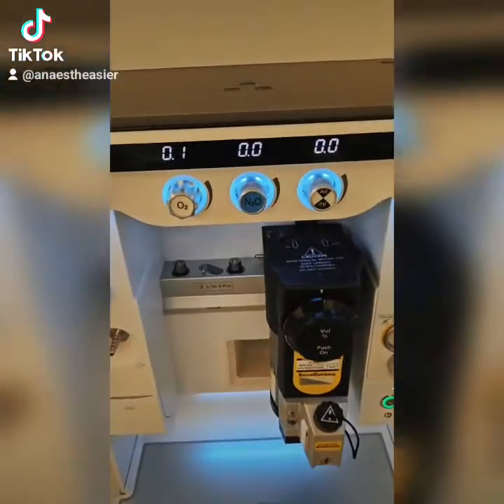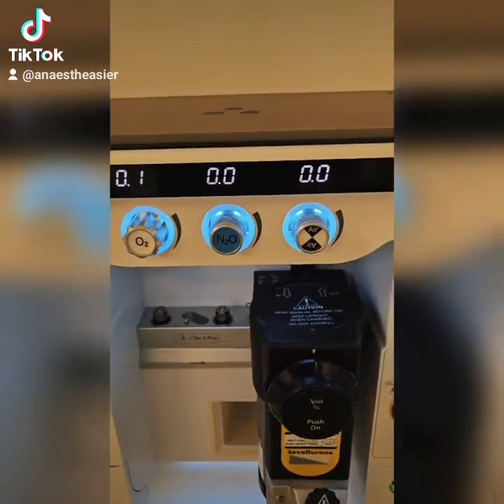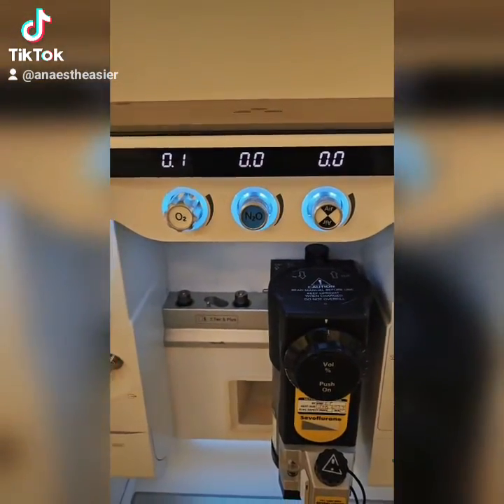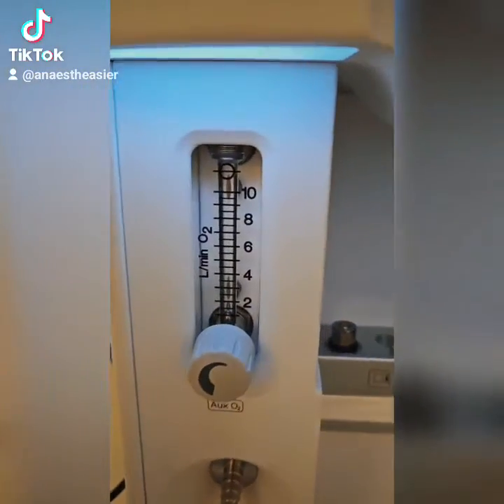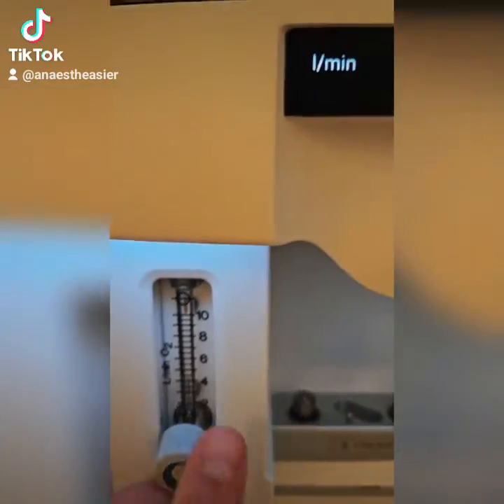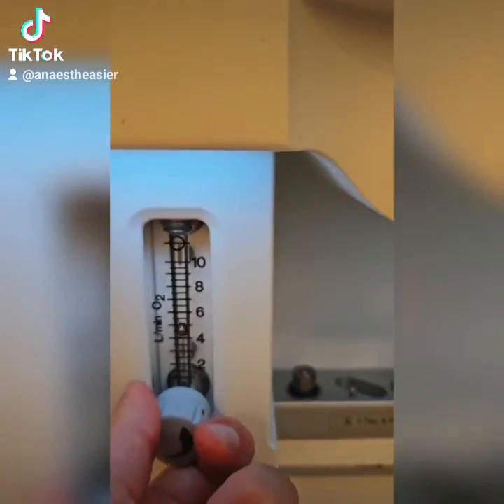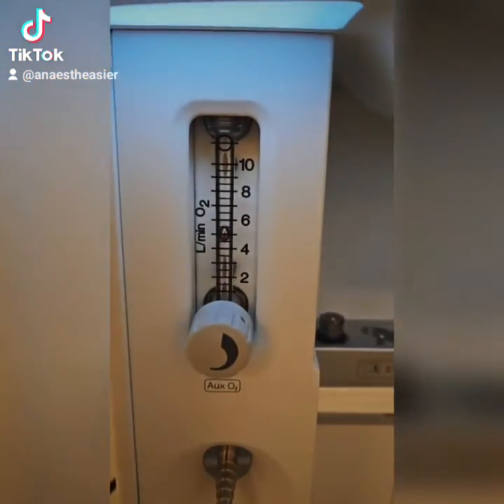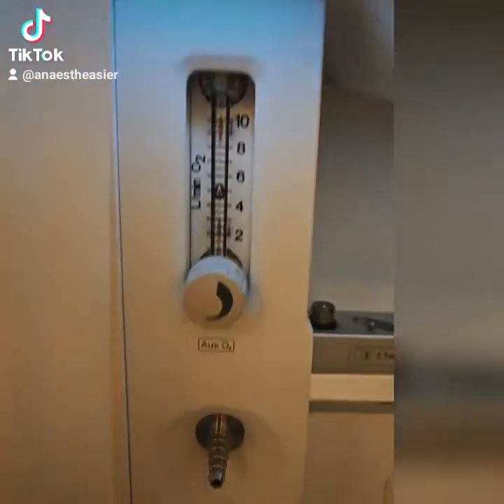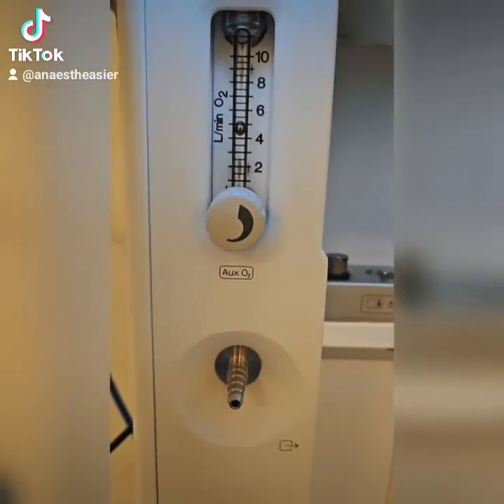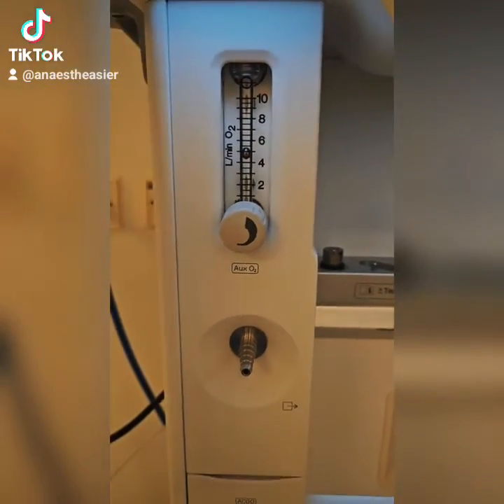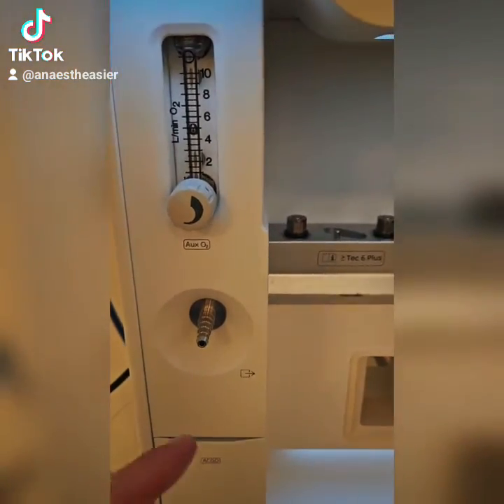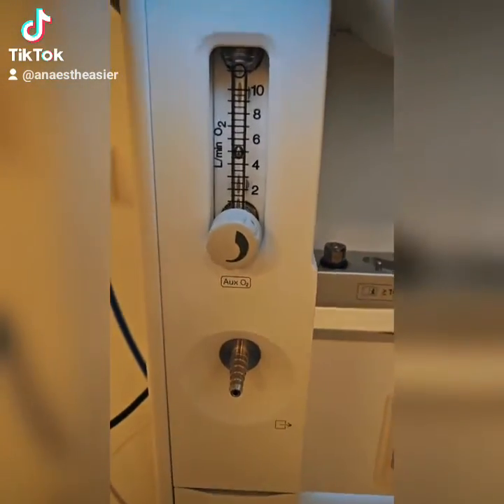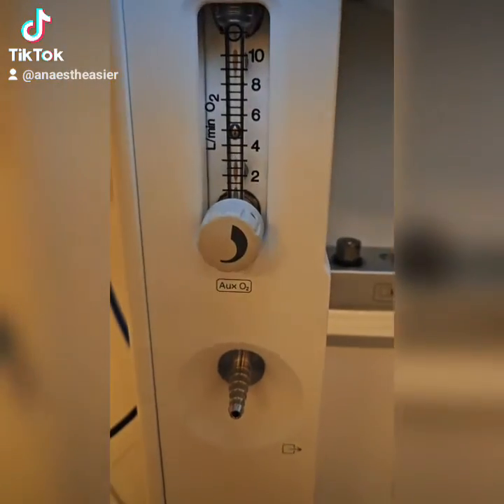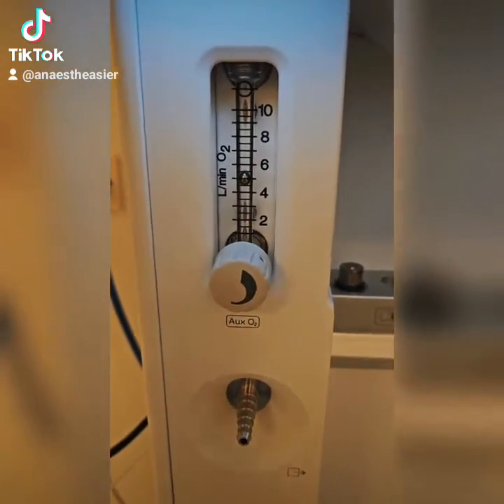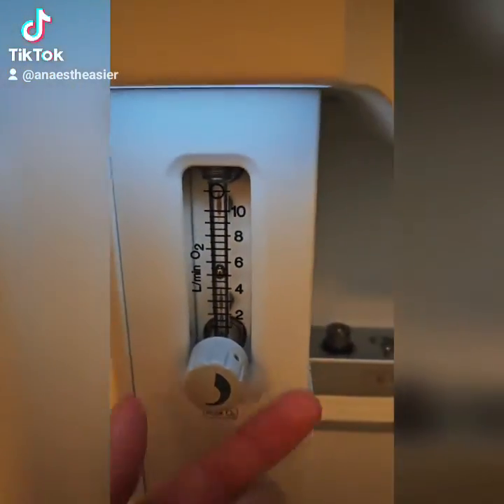Coming around to the front, we have the rotometers. So modern machines don't have these dials anymore. The old-fashioned ones all kind of look like this. So if you want to give a gas, you open up the dial, and you can see that that's starting to give some gas. You can see it coming out. Now this is actually an auxiliary oxygen supply. So this is just a spare backup in case the machine fails. This is just connected directly to the wall, and the oxygen just comes out of this little outlet here. So this is not part of the intrinsic rotometer system. It's just a backup oxygen supply, but that's how the old-fashioned rotometers would work.